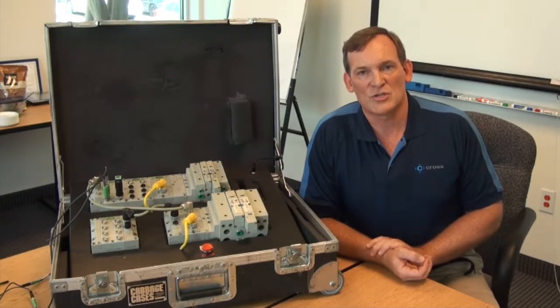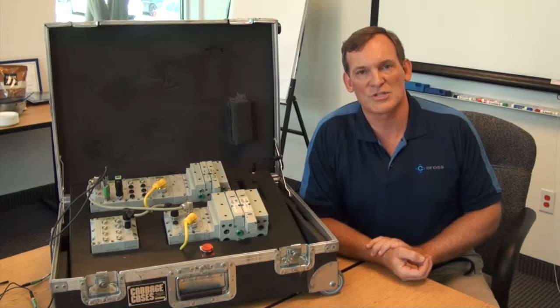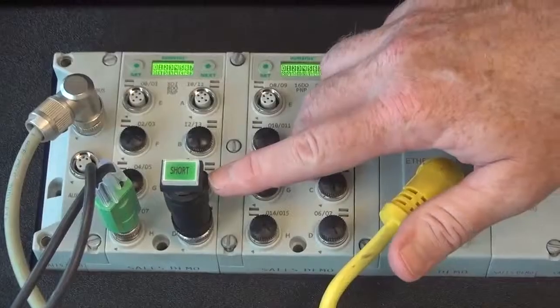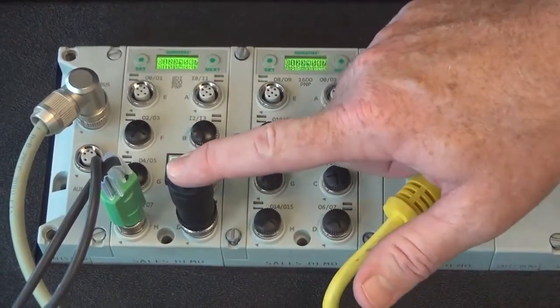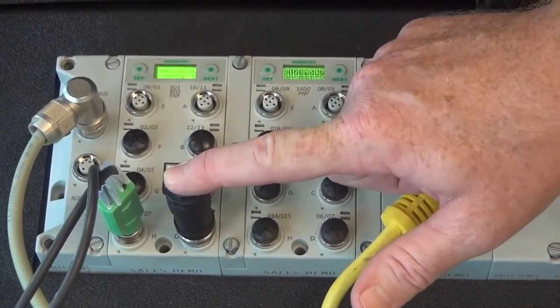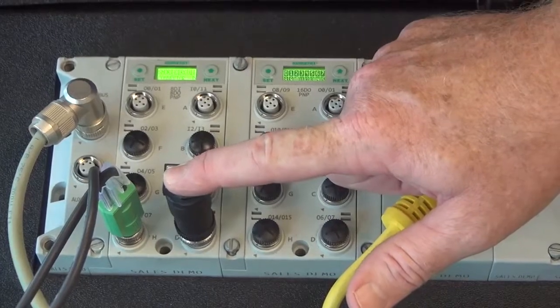The graphical displays on the communication node and I.O. modules serve another purpose. Each shows the status of the module at all times. Should a fault occur, the display indicates the type of fault detected and its location. The display also blinks until the fault is cleared.